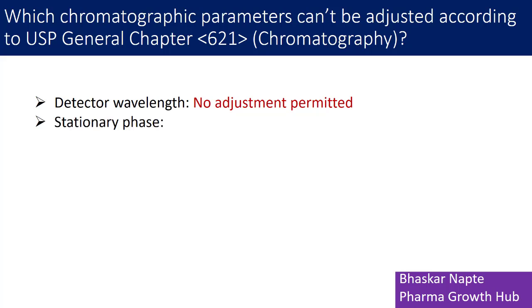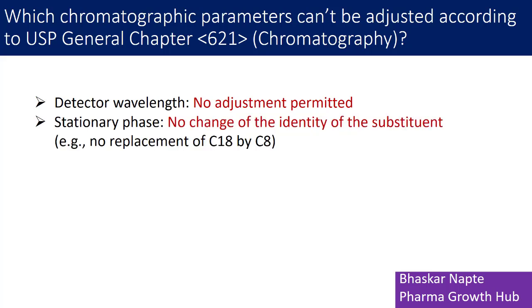The second important parameter is the stationary phase, or column chemistry. According to USP General Chapter 621, no change of the identity of the substituent is allowed. For example, no replacement of C18 by C8. You can alter the dimensions of the column — you can have a different particle size or adjust the inner diameter — but the stationary phase cannot be adjusted according to USP General Chapter 621.